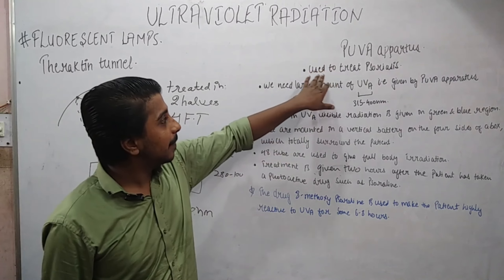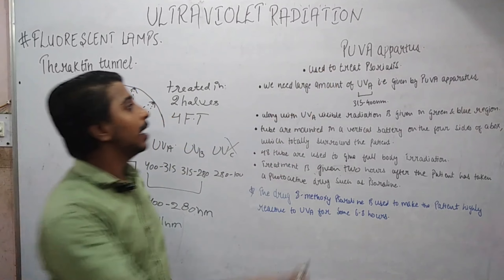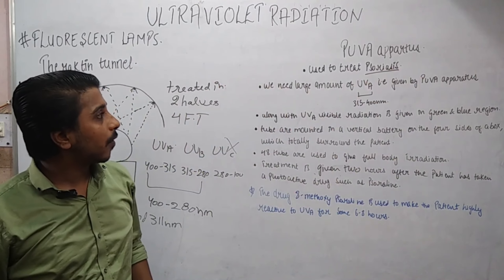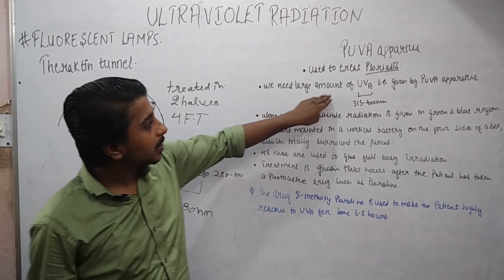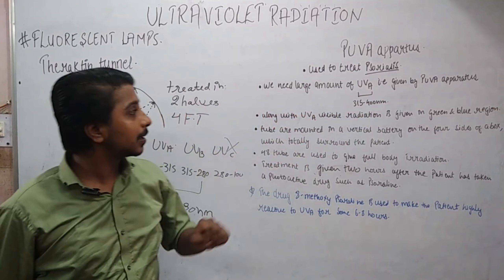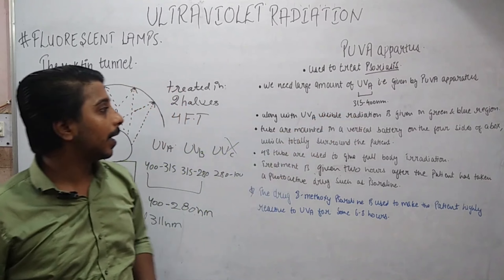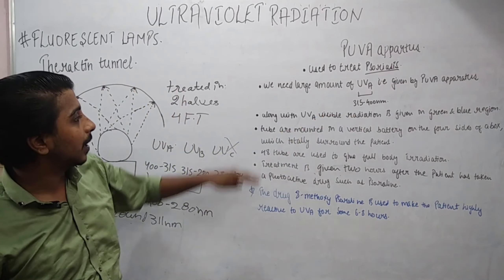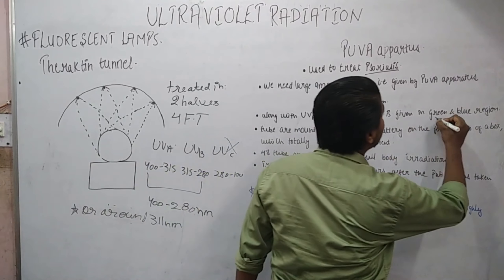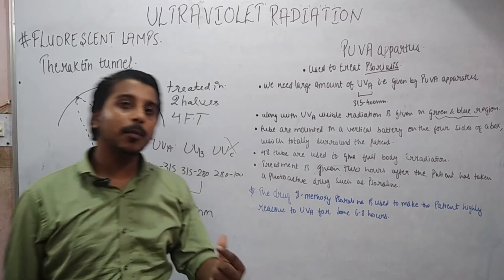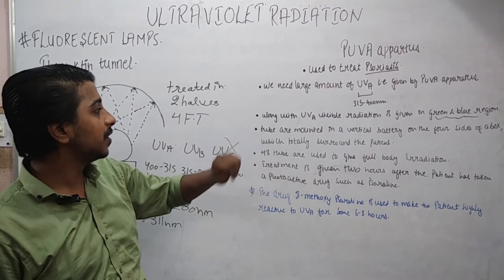Now we will move toward the PUVA apparatus. As the name suggests — psoralen UVA — it is used for the treatment of psoriasis. We need a large amount of UVA, which is given by the PUVA apparatus. UVA is 315 to 400 nanometers. Along with UVA, some visible radiation is given, which is green and blue. From the UV spectrum, only UVA is given.